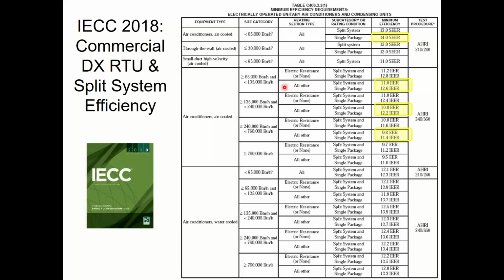All right, but here, if I look at gas heat, which is most rooftops, I need to be 11 full load, 12.6 IEER part load. And as it goes up in sizes, it becomes less and less difficult for the manufacturer to hit that because the manufacturing volume is pretty low on these guys down here. And I'm pretty restricted from a size standpoint to get more surface area. But small stuff is getting more and more and more efficient.